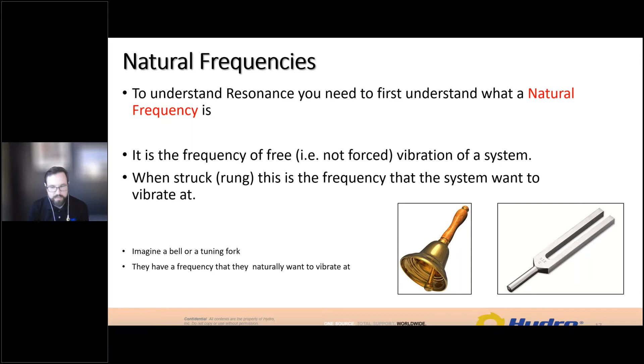So machines, just like a bell or a tuning fork, have natural frequencies as well—they're just properties of the machine, and can differ on different parts of it. The bearing housing on one end will differ from the other end; the casing of a pump will have different natural frequencies than the rotating element. But they all depend on mass and stiffness, shown in this equation: omega, the natural frequency, depends on the square root of k over m, k being the stiffness and m being the mass. Recall the simple spring-and-mass system example—the stiffness of that spring and the size of that mass determine the natural frequency of that system. In that undamped condition, that natural frequency is what drops out of the equation.